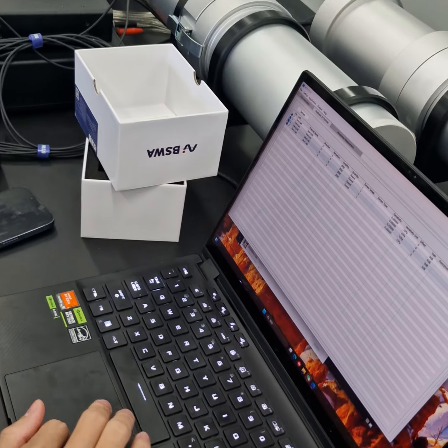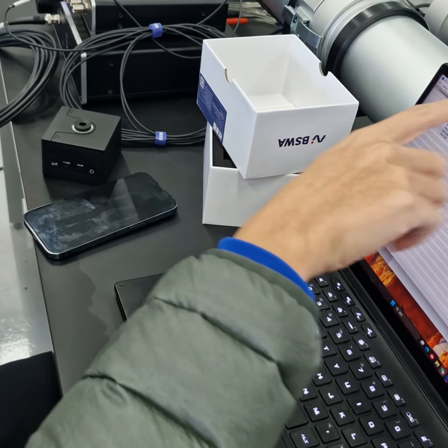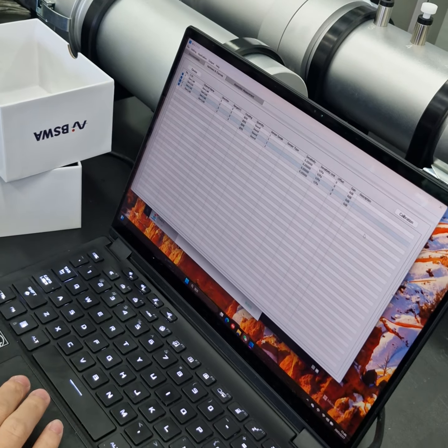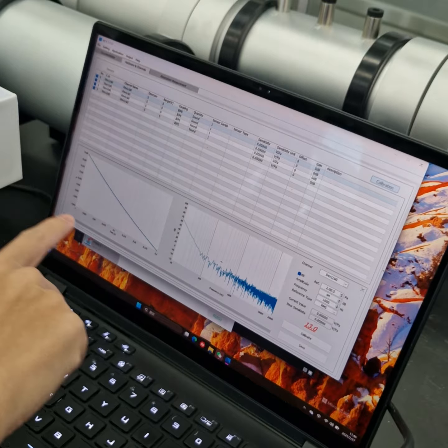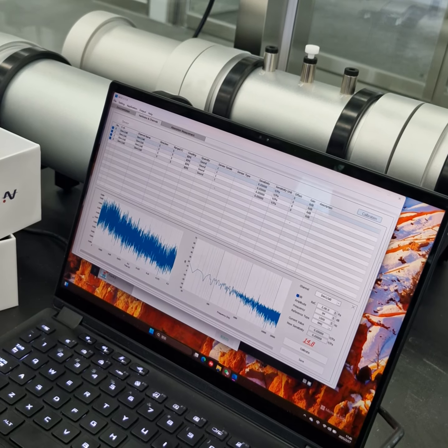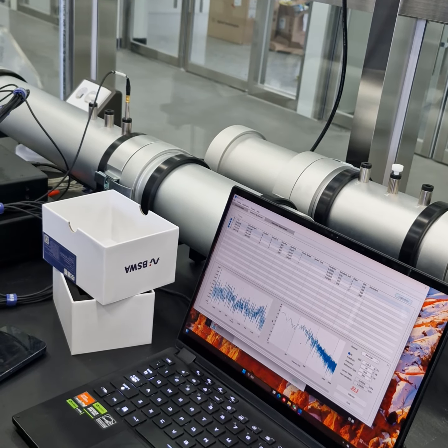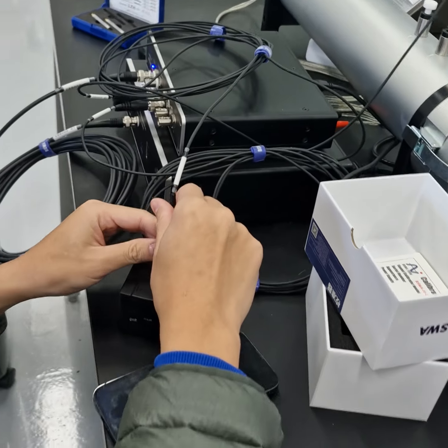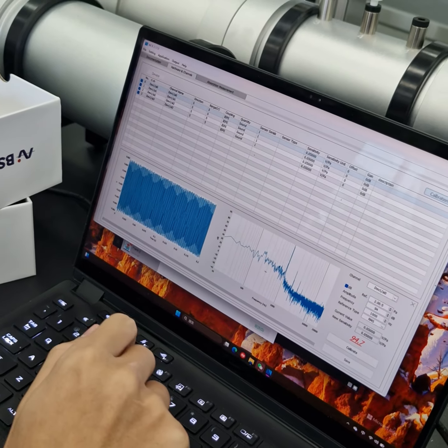Before we start, we have to calibrate the microphone, before in the set hardware channel. There's a calibration button. We click here, and we can see the signal of the channel. This is channel 1. What you do is put the microphone in here, and then turn on the calibrator. See, this is working. This is not normal, this is normal.